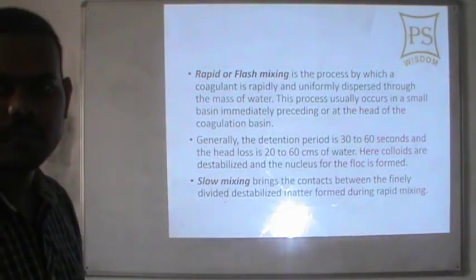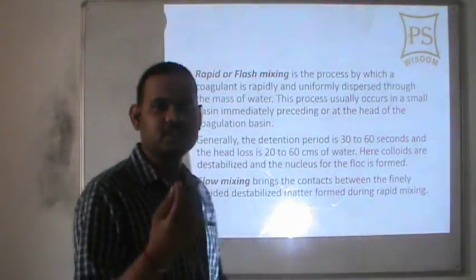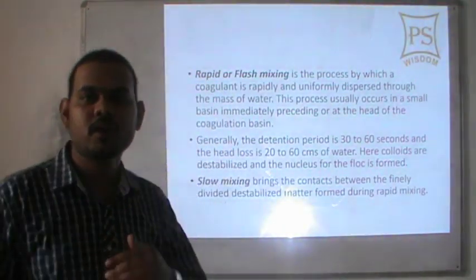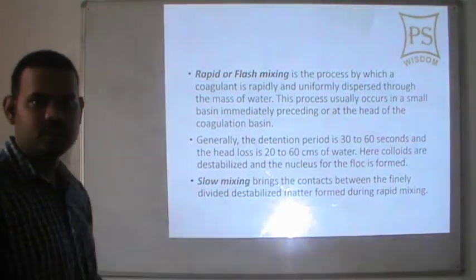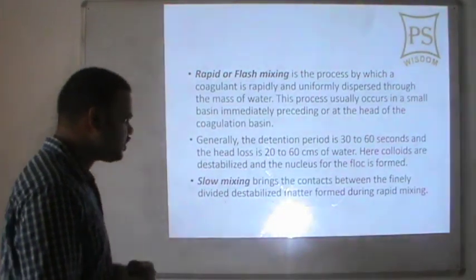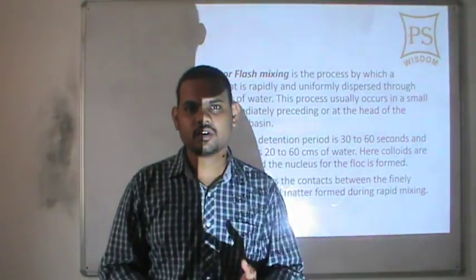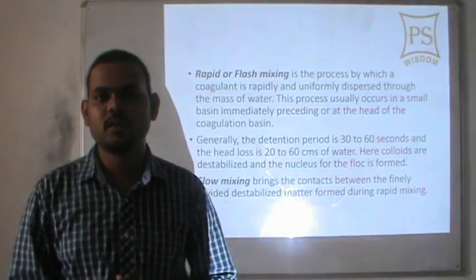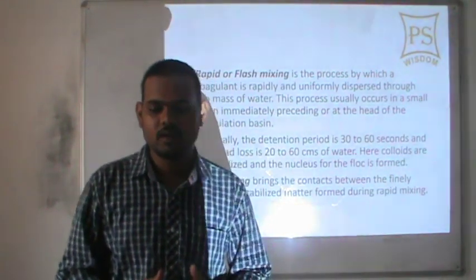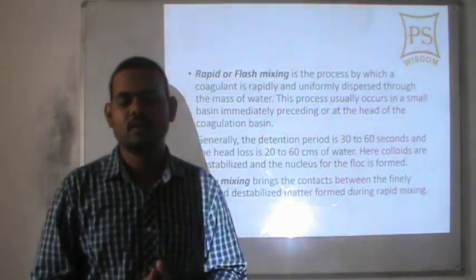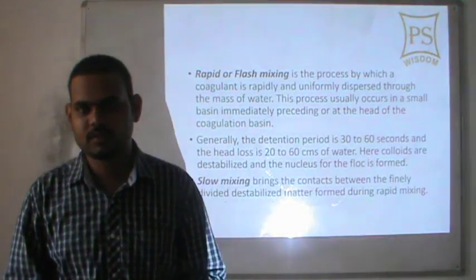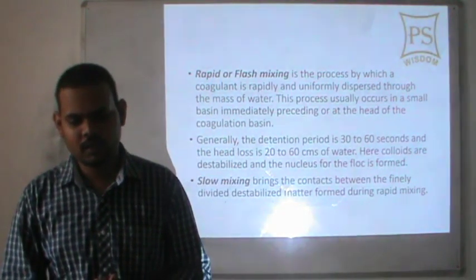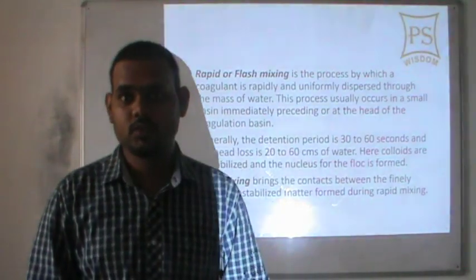In rapid or flash mixing, the nucleus for the flocks is formed. Then the full flocks are formed in the later process known as slow mixing. The retention period is generally 30 to 60 seconds — the water is detained for a maximum of half to one minute after mixing with the coagulant — and the head loss is 20 to 60 cm.